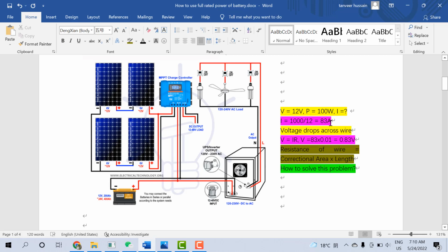83 amps is quite a high current. Due to such high current, the wire can heat up. Due to the heat, the temperature coefficient causes the resistance of the wire to increase slightly. For example, the resistance of this wire goes to 0.01 ohm. That's a very small resistance, but in that case the voltage drop in the wire would be 0.8 volt.